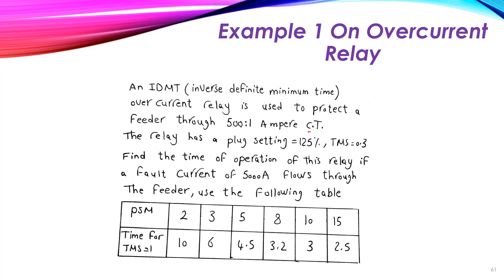The current transformer steps down 500 amperes to 1 ampere — that is its ratio. The relay has a plug setting equal to 1.25, meaning the relay will operate at 1.25 times the rated ampere of the CT secondary. The Time Multiplier Setting (TMS) equals 0.3. Find the time of operation of this relay if a fault current of 5000 amperes flows through the feeder.